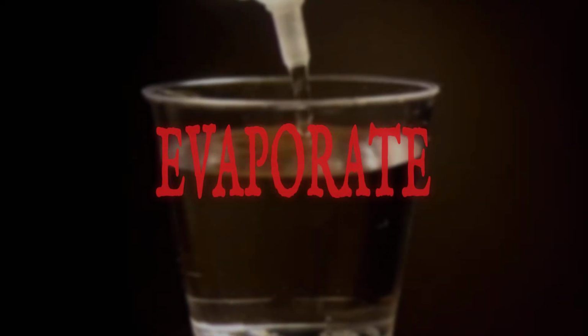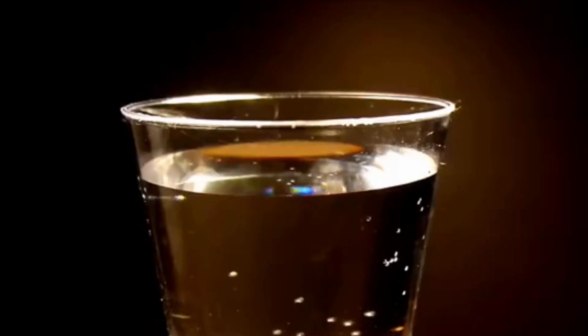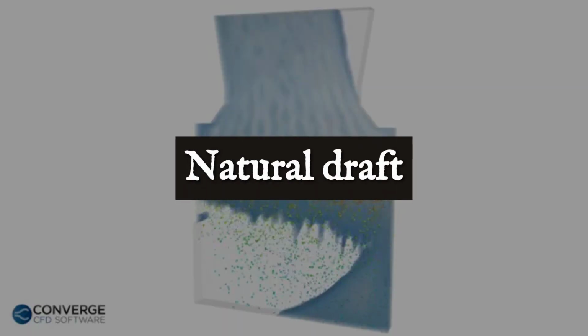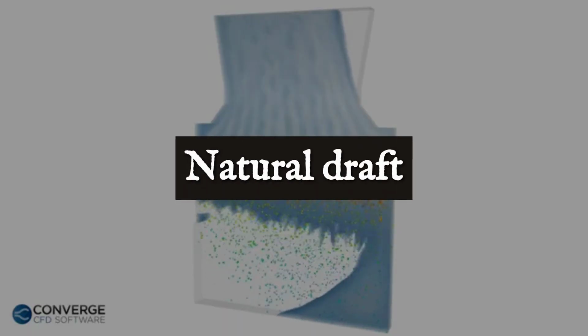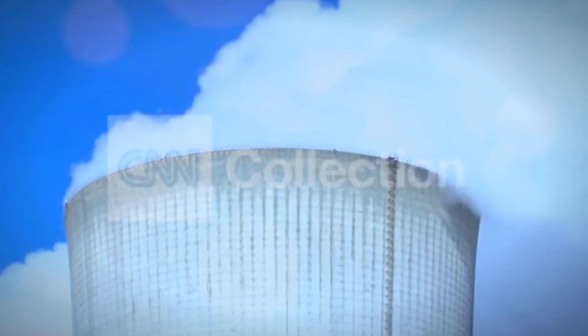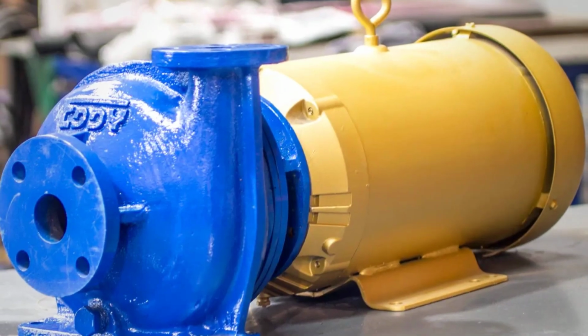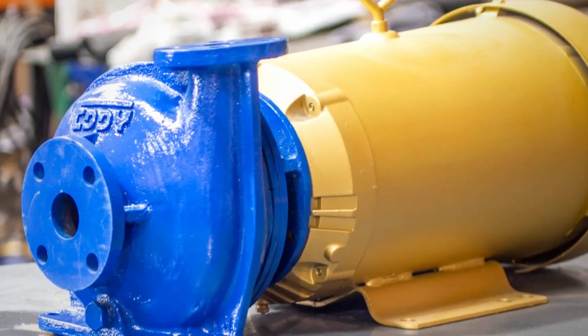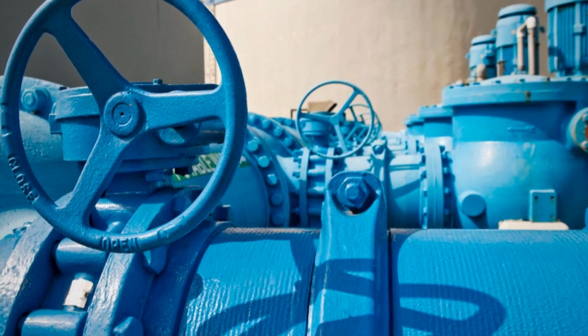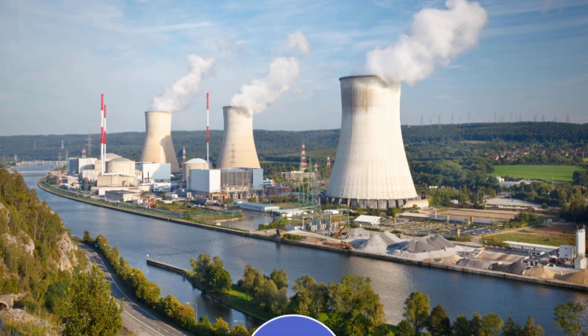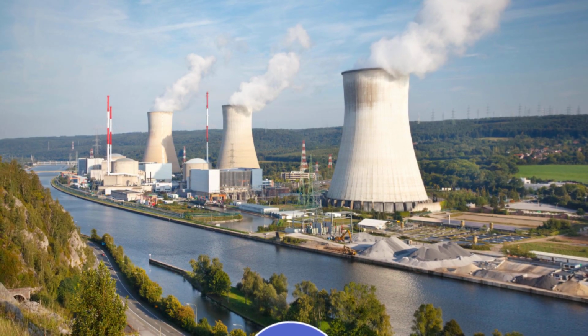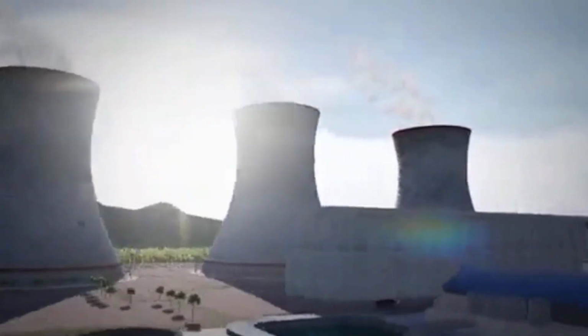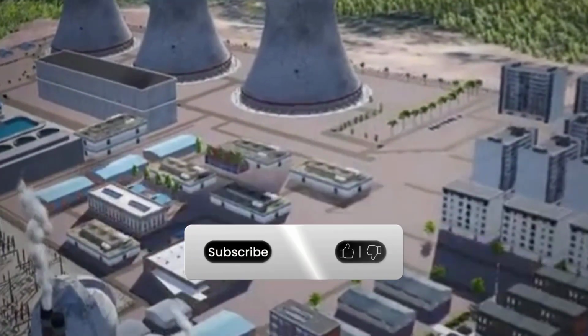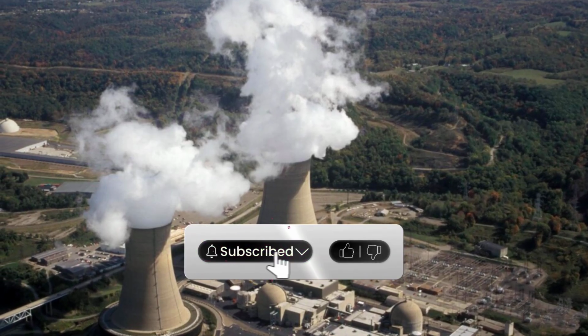Simultaneously, some of the hot water evaporates, removing additional heat and making the air even more buoyant. This dual process not only cools the water but also generates a powerful natural draft, continuously pulling in fresh, drier air. Remarkably, apart from the pumps and minor control systems, these towers operate with no moving parts. For just the energy cost of spraying water, an enormous natural convection current is created, drawing vast volumes of air into the base, up through the fill, and out the top, efficiently rejecting massive amounts of heat into the atmosphere.